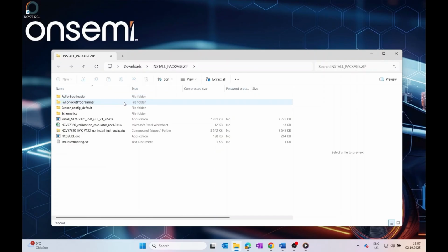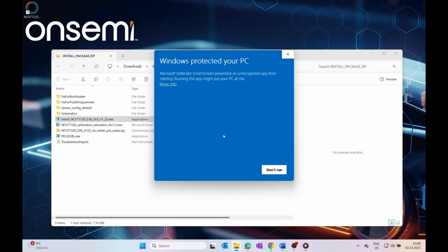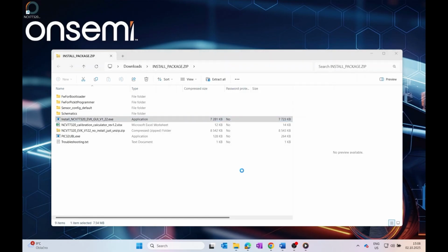Firmware for use with a PicKit programmer. Default sensor configuration files, which can be loaded and programmed via the GUI. Schematics for both the motherboard and sensor board. An Excel-based calculator to help compute the direct coupling compensation, DCC, for improved sensor accuracy. The bootloader application and the installation file. To install, run the setup file. If prompted, select Run Anyway.